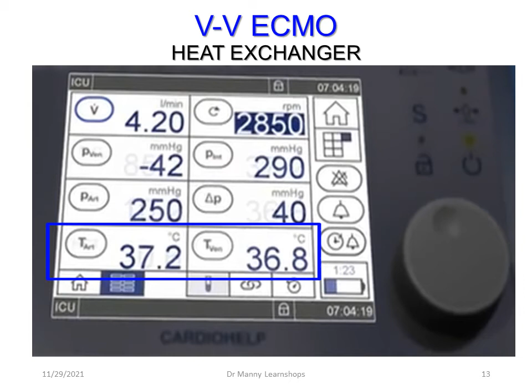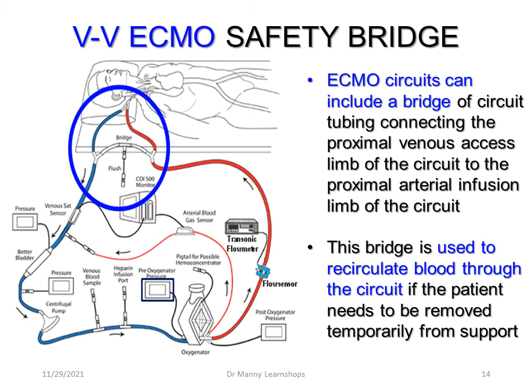Now, there's also something called the safety bridge, and it's highlighted there in blue. Now, most ECMO circuits include a bridge, and this is a circuit of tubing connecting the proximal venous access limb of the circuit to the proximal arterial infusion limb of the circuit. And this bridge is used to recirculate blood through the circuit if the patient needs to be removed from the circuit temporarily for support, or there's an emergency situation. The patient could have arrested, so therefore the bridge can be used to recirculate blood through the circuit while the patient's being resuscitated. Or there may be a problem, for example, with the exchanger. The oxygen exchanger needs changing, so therefore blood can be recirculated while the patient is being still treated.